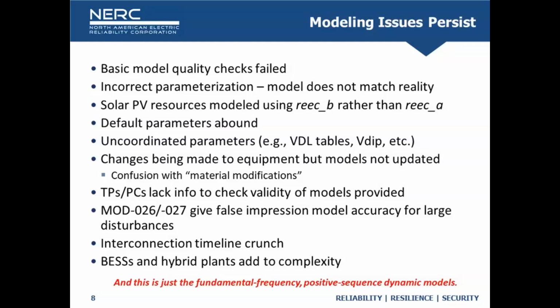TPs and PCs often lack information or data to perform validity checks or verification checks. Do I have a screenshot of a plant controller setting sheet, a spec sheet, an inverter spec sheet, or a one line diagram? Do I have all that stuff as a planner to verify that the model I received matches a reasonable assumption of what this facility is doing? We hear time and time again that transmission planners say, I get a model, I have to trust it because I don't get anything else. I think we've all come to realize that's a failure of the interconnection requirements, because you should require suitable documentation to come along with that model to verify that the software version, settings, and controls match the field settings reasonably. We need to be able to perform those validity checks on all sides to make sure the model is reasonable.